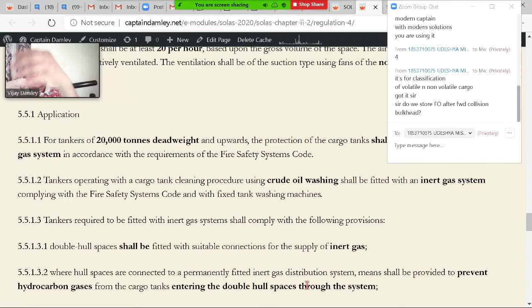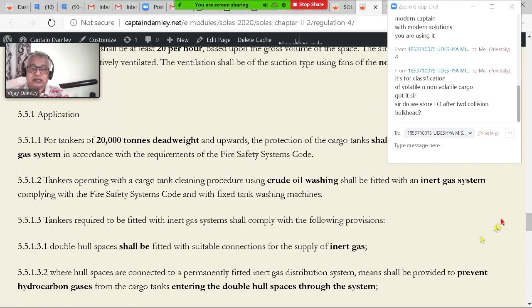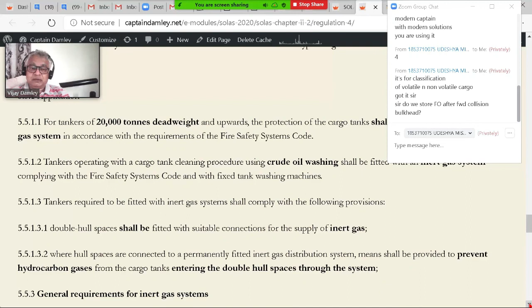I connected a pipeline to provide inert gas, but there was a leakage and the gas went in along with vapor. Now that is dangerous, because the inert gas was so many percent, the flammable vapor percentage is so much, and then it finds oxygen. Then it becomes explosive. This is the reason. So even the system has to be protected so that by accident it should not happen. In simple words, the inert gas supplied to the tank, the cargo tanks I'm talking about, must have a blockage arrangement for reverse flow, non-return valves. So by accident also it will not have a reverse flow.